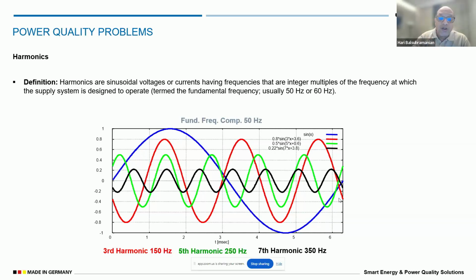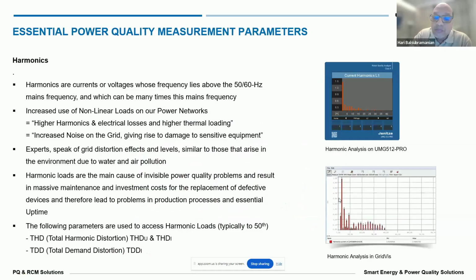So how do we classify the harmonics? Till now, most of us know a parameter called total harmonic distortion, which takes into account all the harmonics present in the waveform. There is a technique called the fast Fourier transform, which is applied on the samples we are getting, and then we separate the different frequencies with it. That's how the harmonics are calculated. Then these harmonics are totaled with a formula and divided by the fundamental. I will show you the formulas right now. Then it is called total harmonic distortion.